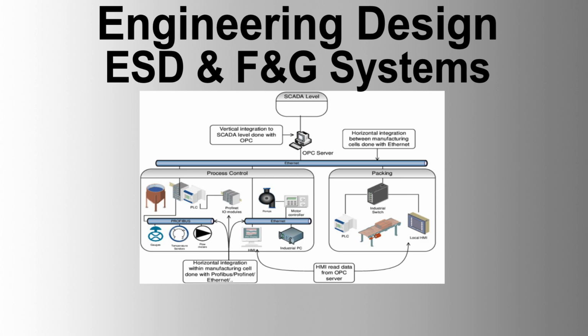General requirements. 1. Online logic reload. The system shall allow for online reloading of logic changes without causing a shutdown, with detailed procedures and precautions provided by the vendor. 2. System synchronization. The system must synchronize with the DCS master clock, ensuring time accuracy within 10 milliseconds. 3. Safety integrity level, SIL. The system design shall meet safety integrity level SIL 3 requirements and be TÜV certified.